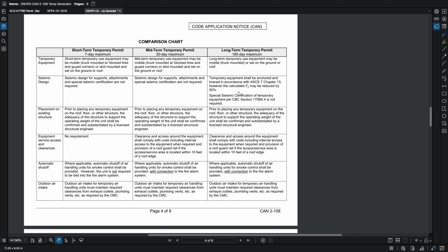A side note to add is that if you have a temporary generator, usually on a trailer, that's very high off the ground, so that has some large seismic forces. If you are doing that, you either need to recognize you're going to have to anchor something that's 15 feet in the air with a high center of gravity, or have one that can be sat on the ground, which will significantly reduce the amount of anchors you need.